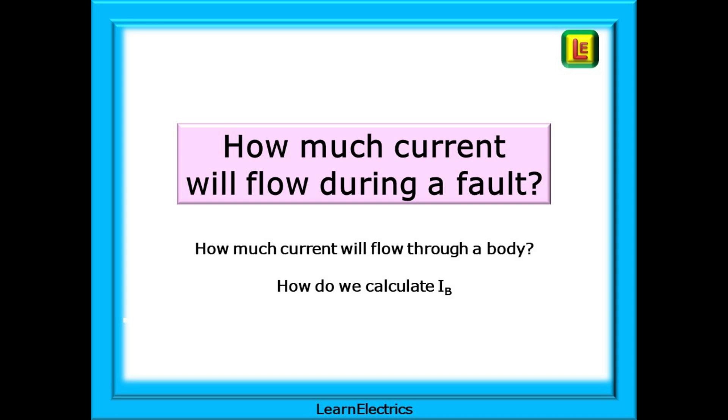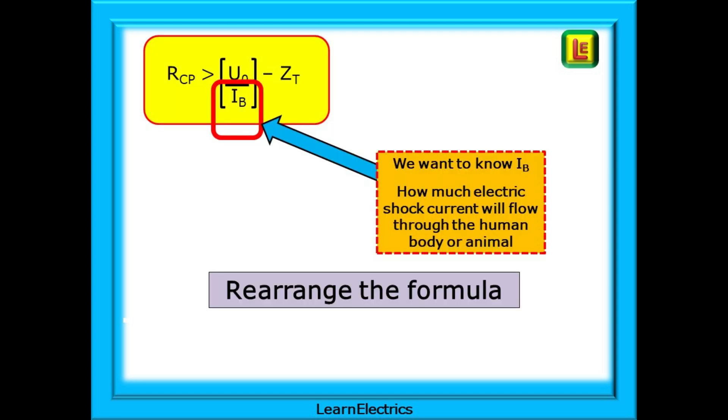Of greater usefulness, in my opinion, is finding out how much current might flow through the body during a fault, and then making a bonding decision based on the current value, or IB. There's no formula for this in the book, so how are we going to calculate it? We want to know IB, how much electric shock current will flow through the human body, or livestock, if we have measured RCP. To do this, we just rearrange the original formula. Let's look.